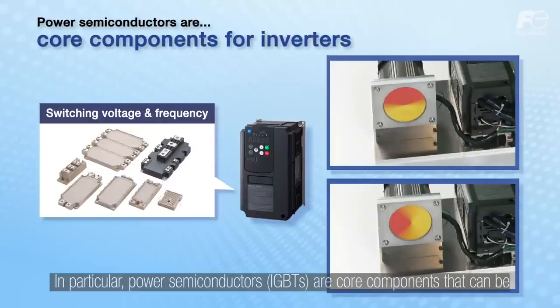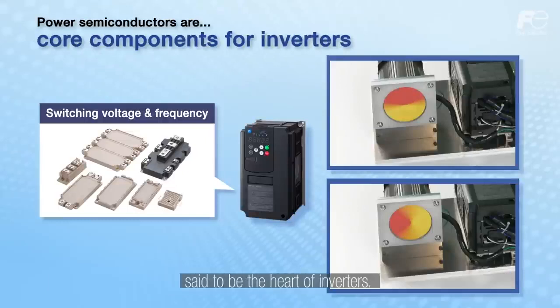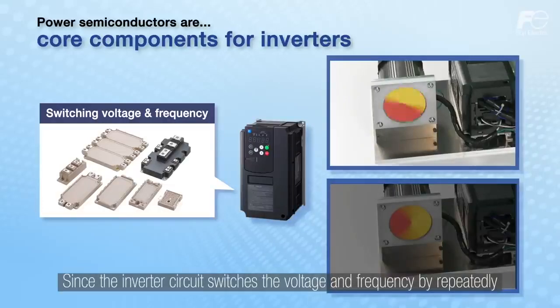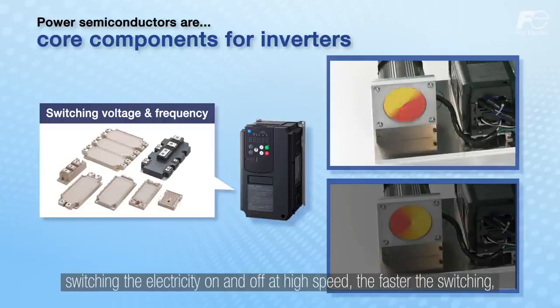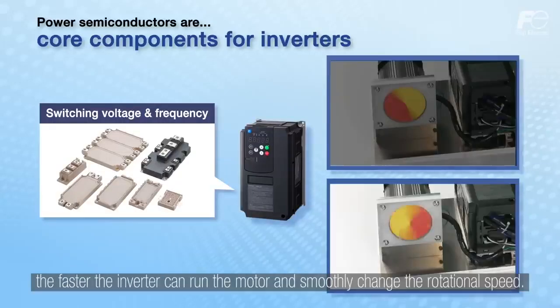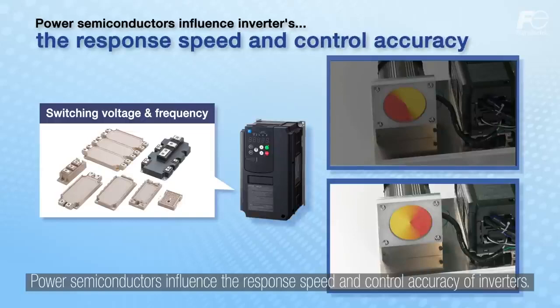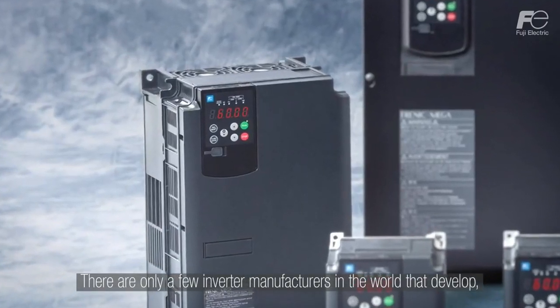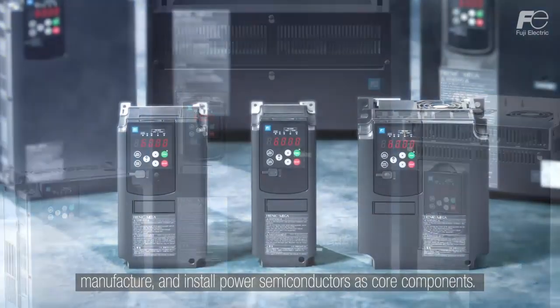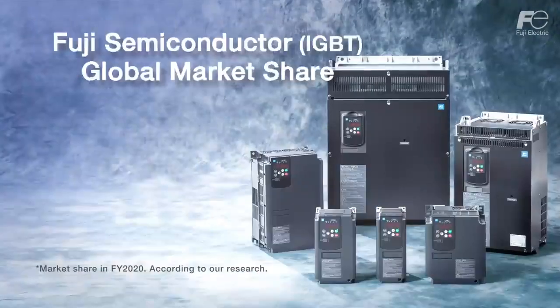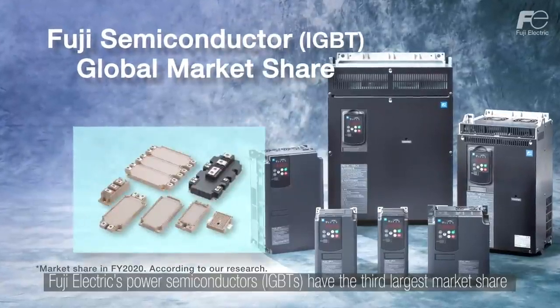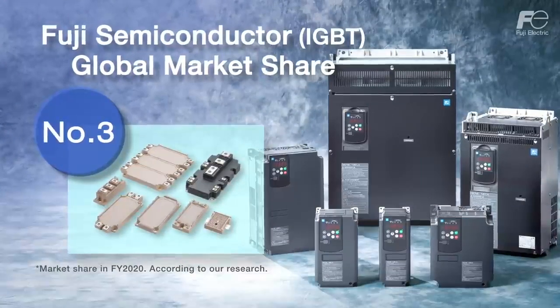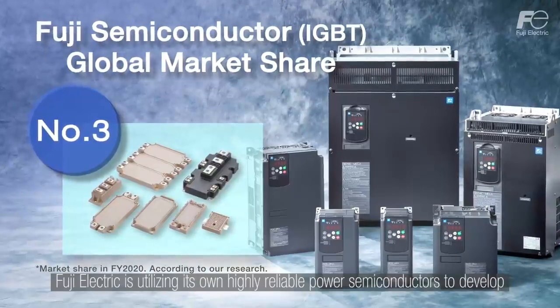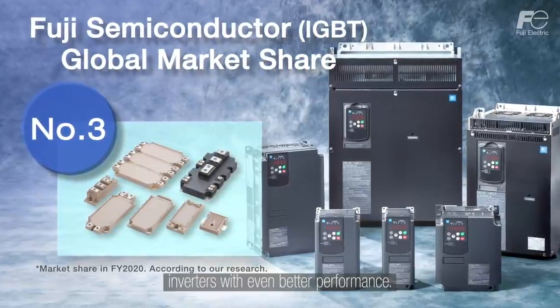In particular, power semiconductors, IGBTs, are core components that can be said to be the heart of inverters. Since the inverter circuit switches the voltage and frequency by repeatedly switching the electricity on and off at high speed, the faster the switching, the faster the inverter can run the motor and smoothly change the rotational speed. Power semiconductors influence the response speed and control accuracy of inverters. There are only a few inverter manufacturers in the world that can develop, manufacture and install power semiconductors as core components. Fuji Electric's power semiconductors, IGBTs, have the third largest market share in the world. Fuji Electric is utilizing its own highly reliable power semiconductors to develop inverters with even better performance.